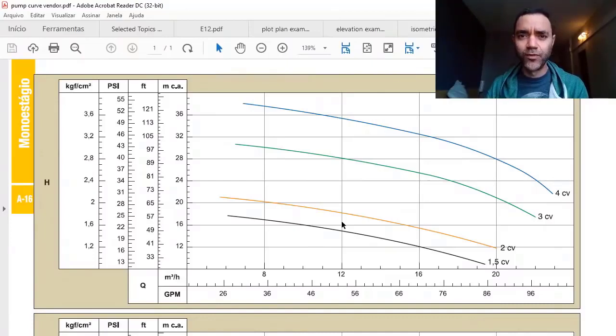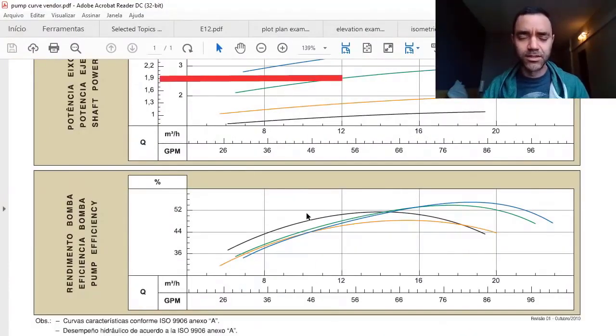If you're doing projects in the oil and gas industry, most often you will need to comply with API 610. There are some requirements for pump sizing and selection. For instance, it talks about the best efficiency point. You can see in this documentation there is no mention to the best efficiency point because it's not following API 610. The API recommends that your pump operates between 90 and 110 percent of your best efficiency point or BEP of your pump curve. To be able to do that, you need a pump curve that shows you where the BEP is, and the BEP is the highest efficiency of the pump.